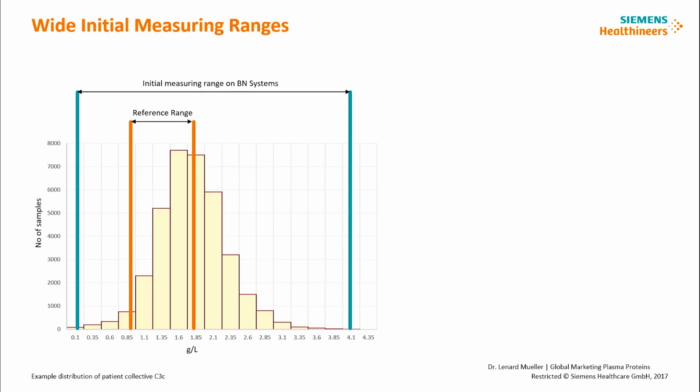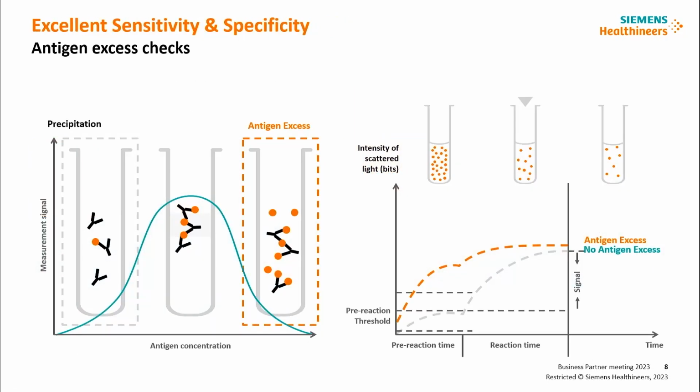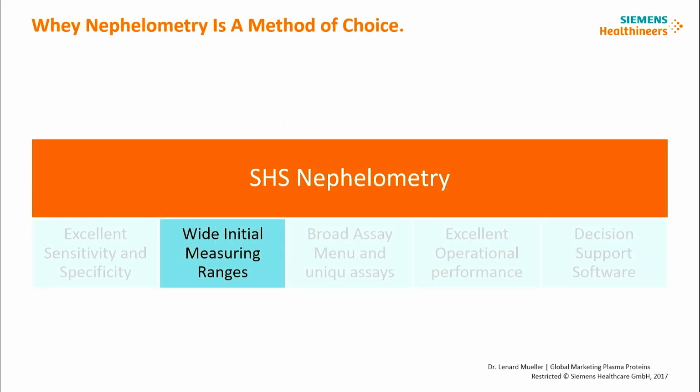And if it is lower than a certain threshold, it means the concentration is low or normal, then it will go to the regular or normal dilution. So when the antigen or the signal is high, the machine automatically will move to the higher dilution, which means it makes a huge dilution of the sample because of the antigen excess, which is giving you the first accurate result. Okay?